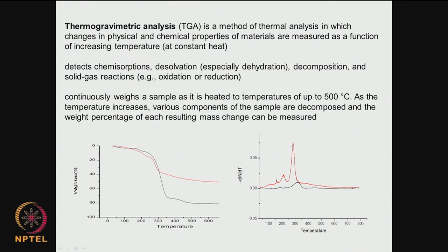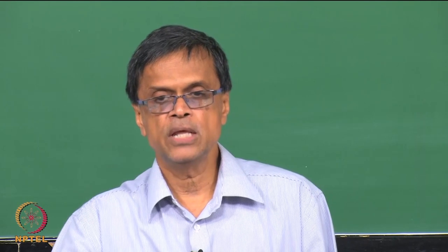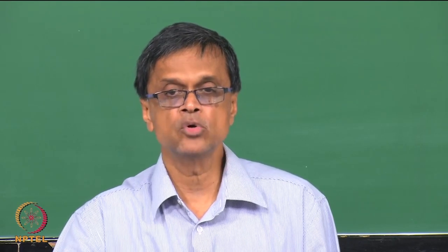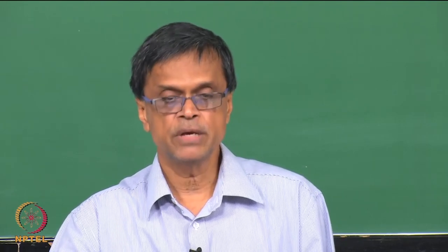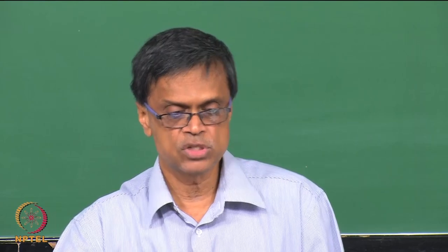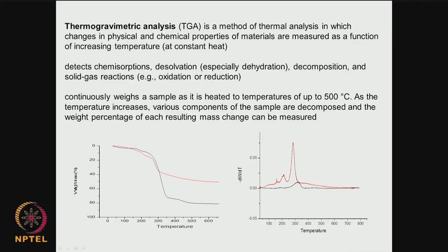TGA is a very useful technique especially in polymeric systems. The temperature at which weight loss starts becoming maximum is a useful value. Sometimes a polymer may show 2 temperatures of weight loss — initially loss of easily removable hydroxyl groups, then at a higher temperature more difficult weight loss. We can detect chemisorption, desolvation, decomposition, and solid-gas reactions. The instrument continuously weighs the sample as it is heated, up to 500, 600, or even 800 degrees.